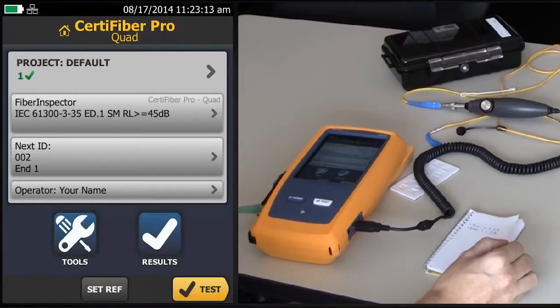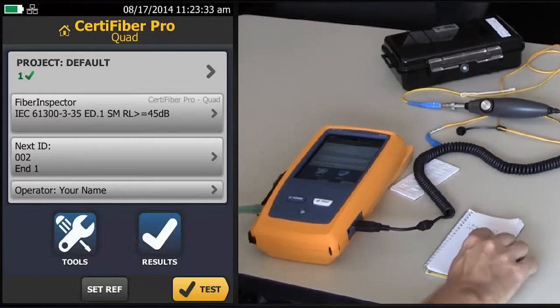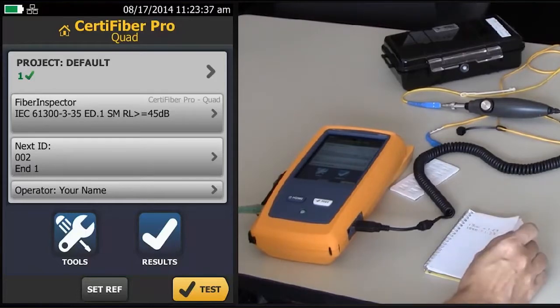You may find yourself operating to a custom loss limit, either you're testing a single fiber, or the consultant or end user, or indeed the cabling manufacturer, has specified a loss limit that's tighter than what the standards actually require. In this case, my calculated loss limit is 1.27 dB for both 1310 and 1550. It's quite a short link.